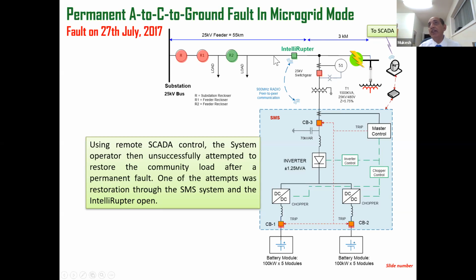Now, if this same fault happens to be here, it will not see a forward fault. Basically, a permanent fault happens here. This will see a fault current coming from here, but it does not recognize it as a reverse fault. I'm going to tell you why later on. The logic is, if I don't see a forward fault, it's a reverse fault. I'm going to tell you why it does not see a reverse fault. That has to do with the battery. I'm going to come back to that later.